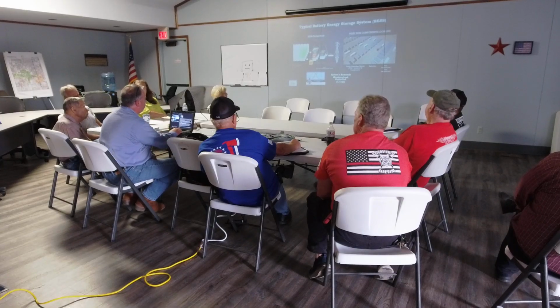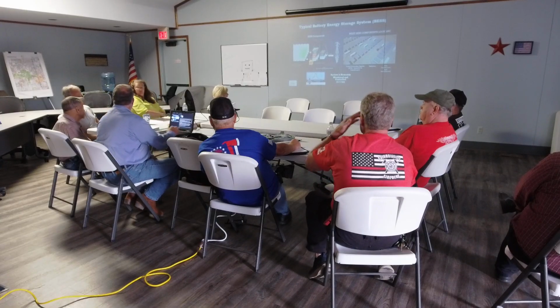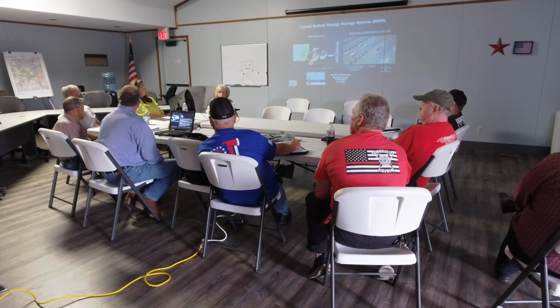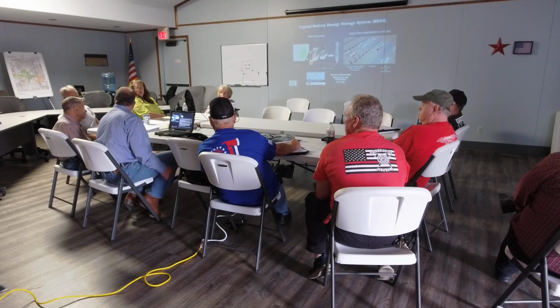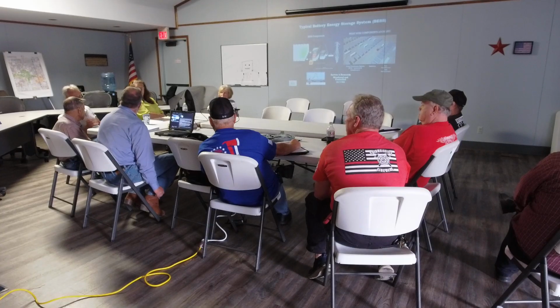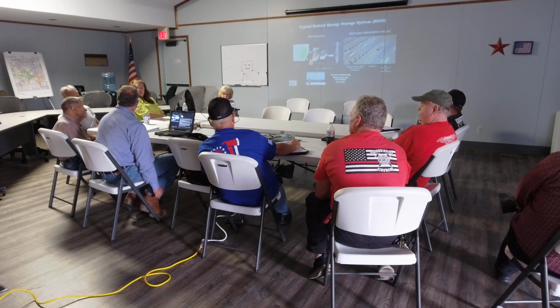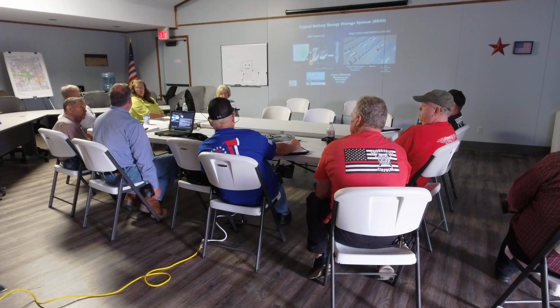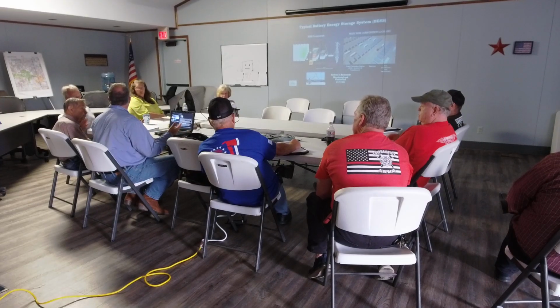We can talk a little bit about tactics too if you guys want. For a rule of thumb on sizing, I've heard that for every 10 megawatts of storage it requires an acre—not sure if that's accurate. Each battery container is typically about 1 megawatt, so a 100 megawatt battery has 100 containers. The average spacing, depending on the battery manufacturer and test results, is usually 3 feet between containers and 10 feet off the ends, so you're talking a 10 to 15 acre battery site.